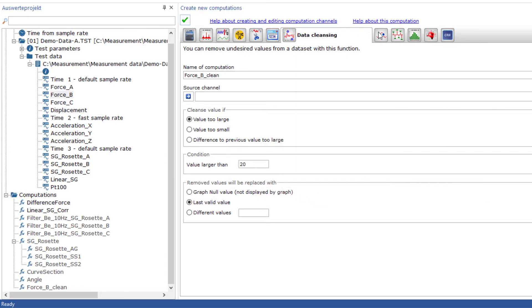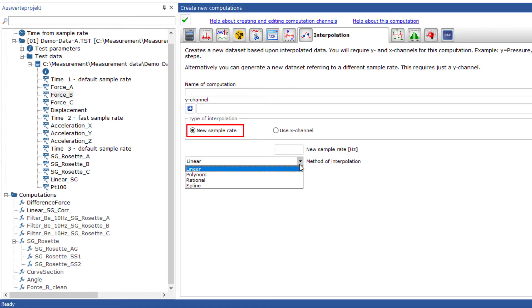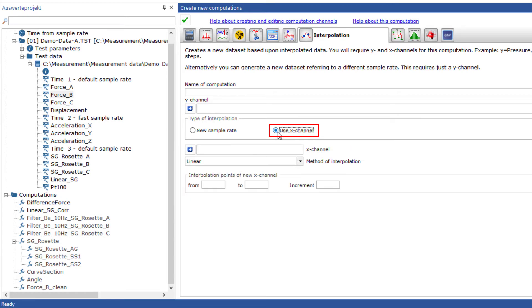The interpolation of measured values is particularly useful for converting measured values to another measuring rate, for example, if the original measuring rate was too high or to normalize it. Normalization is necessary, among other things, to be able to determine the measured values at certain discrete values after calibration or to be able to mathematically compare measurements of force over displacement or torque over rotation angle with other additional measurements.